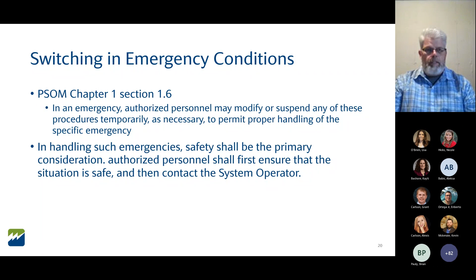If you do have to do some emergency switching, make sure you keep safety in mind. Make sure the situation is safe. If you find something going on and take independent action, PSOM Chapter 1 says if you're authorized and qualified, you can do that. Just realize, don't put it back in. If you have to force something out, don't put it back in when you think it's safe. If you take independent action, stop and then communicate with the system operator. In my mind, the only time I'd see someone take independent action is if life is in danger.